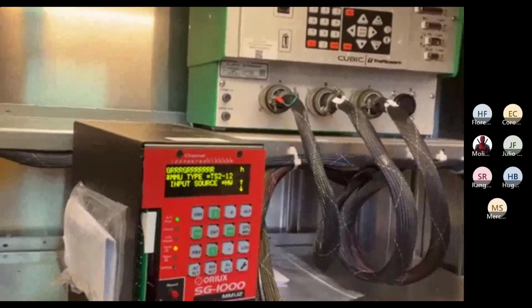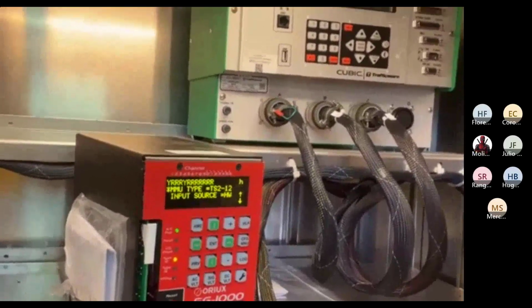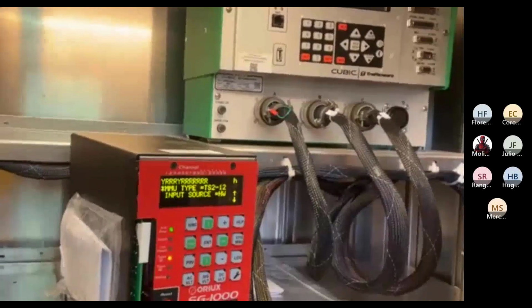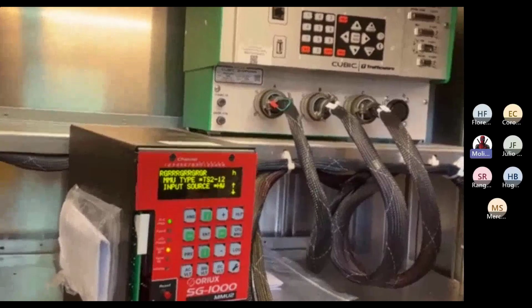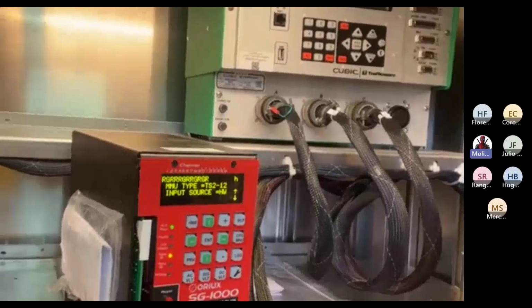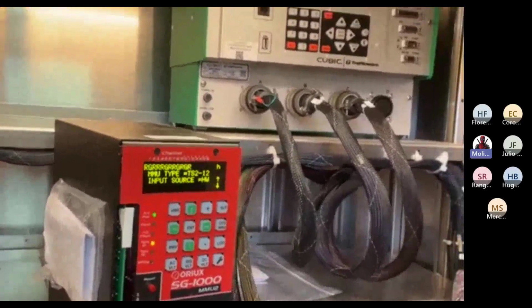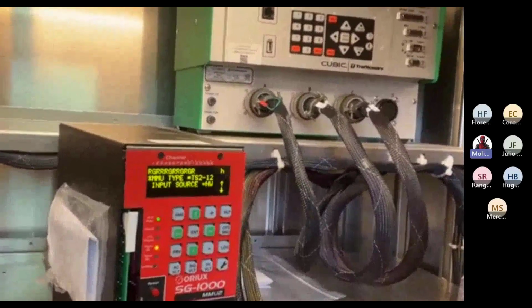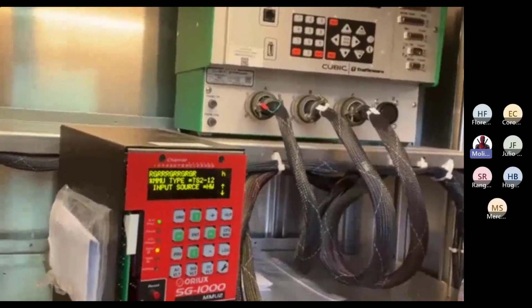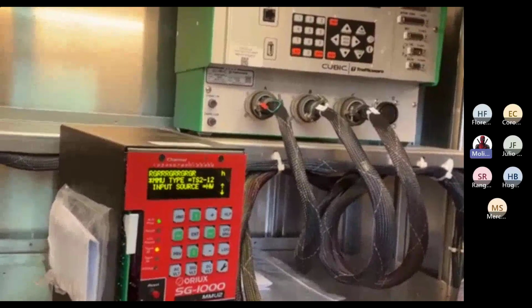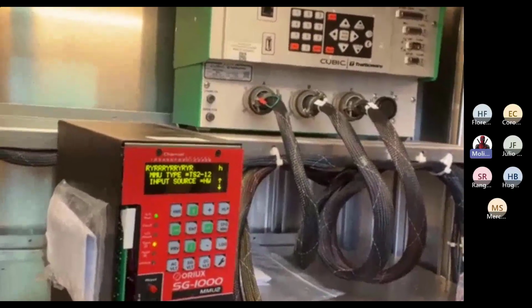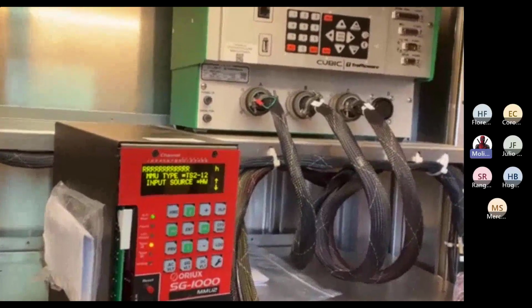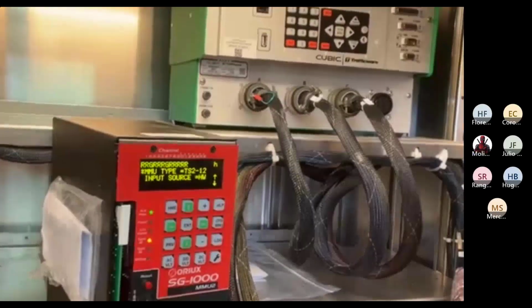If you look on the back panel, there's probably not a terminal that says type select, right? If you wanted to fool it, you'd have to find that wire and apply logic ground to it so that the monitor would think it's a TS2 cabinet. I just want to make sure, so if I have a problem, then I know. But I think it's going to be okay because the other cabinets, they're wired different.